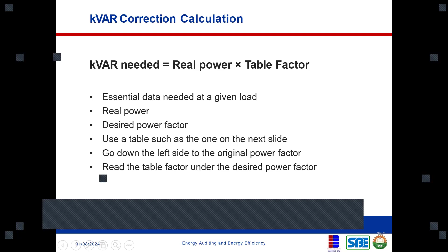So if you come to a facility and notice they're having a power factor issue, look at their original power factor, assuming it's 70 or 0.7, and you want to correct it to 90. All you need to do is trace 70, the original power factor, find the desired power factor of 90, and trace where it intercepts with 70. This gives 0.536. You multiply this value by the real power, and once you do this, you'll be able to get the kVAR. It's a simple and straightforward calculation.